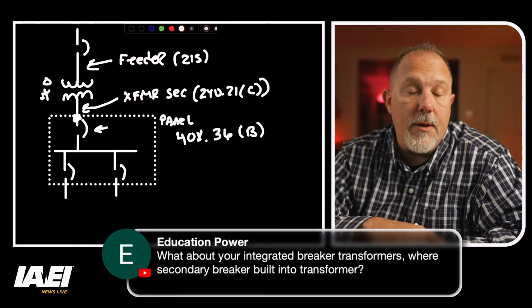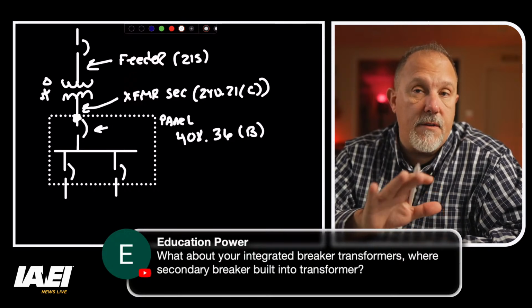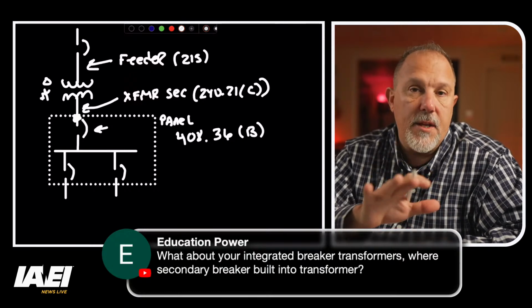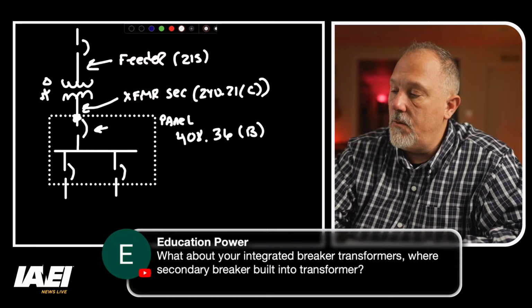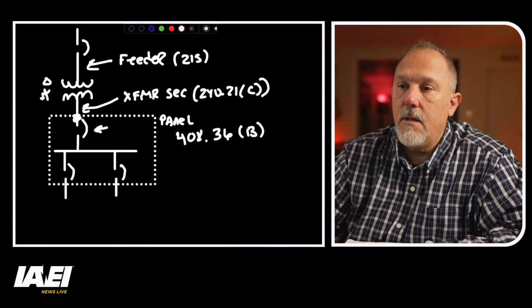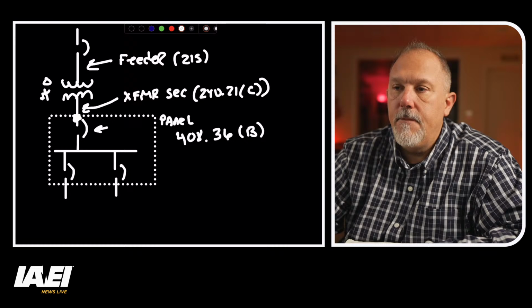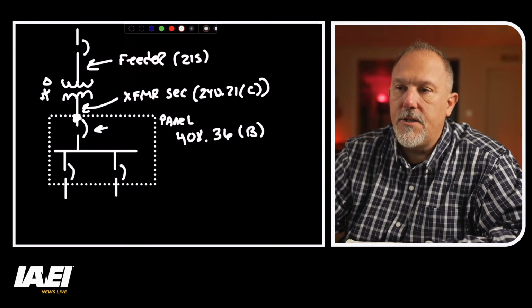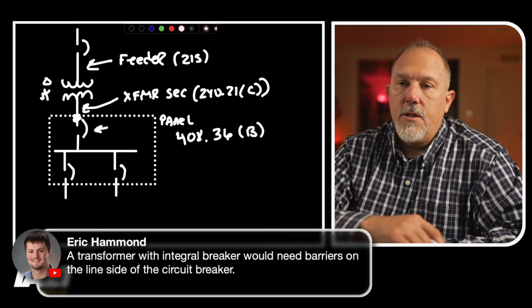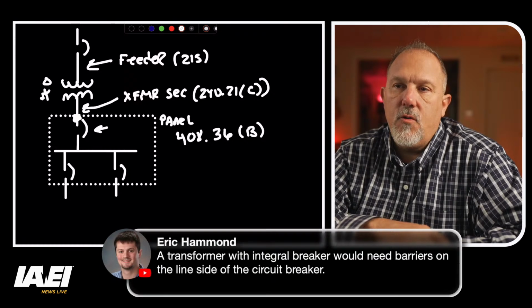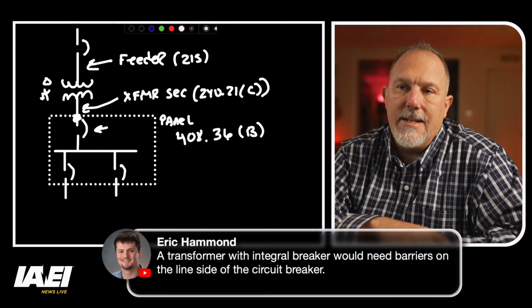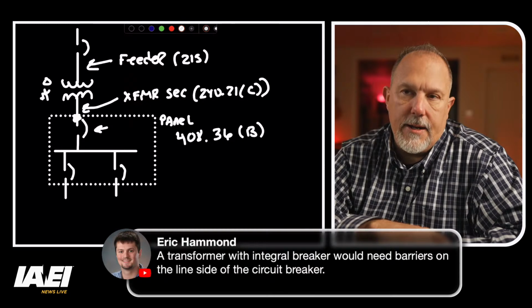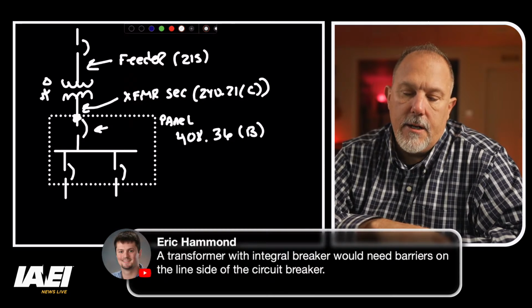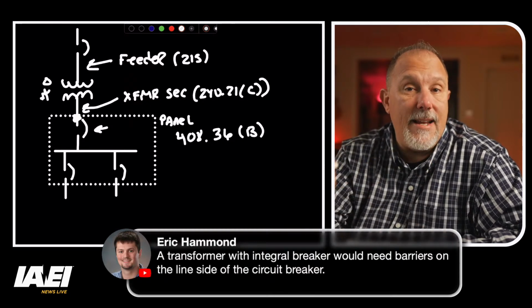conductor, breaker. And we do the same thing in services, right? We do the exact same thing in services. And that's where you would need the barriers. So transformers with integral breakers would need barriers on the line side of the circuit breaker. I would agree with you, Eric. That would be governed though by the standard.